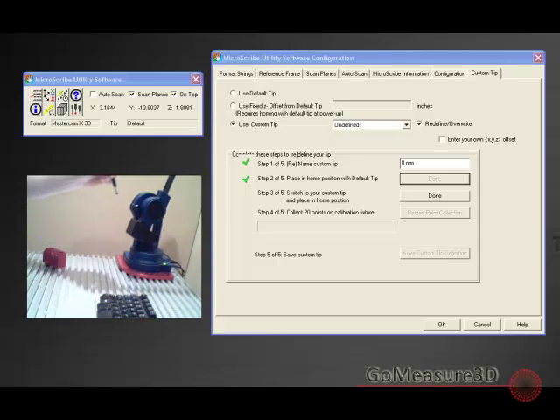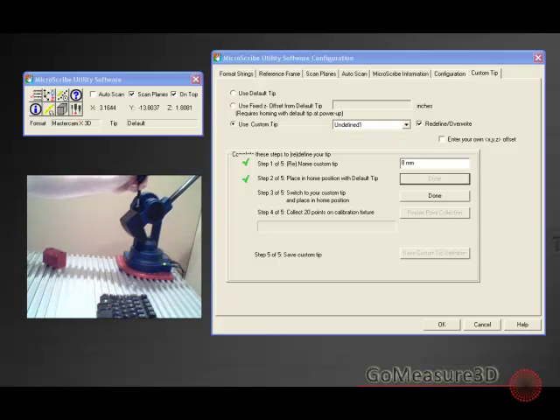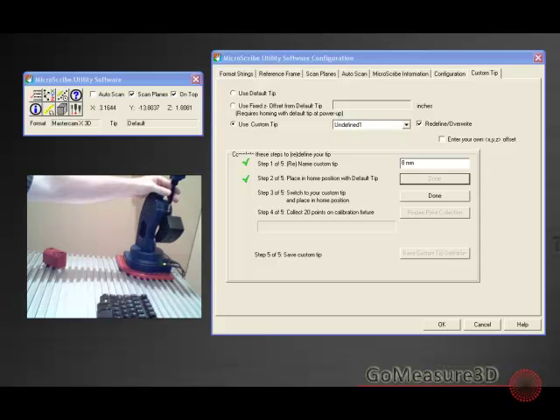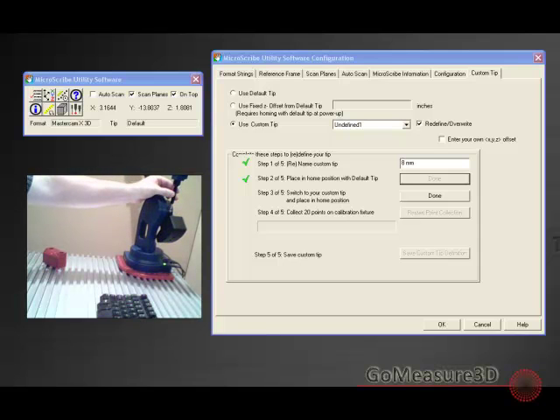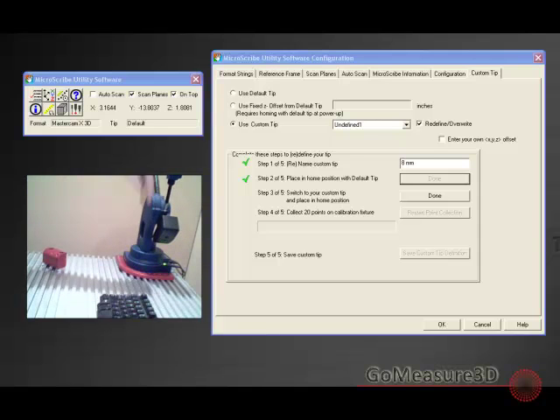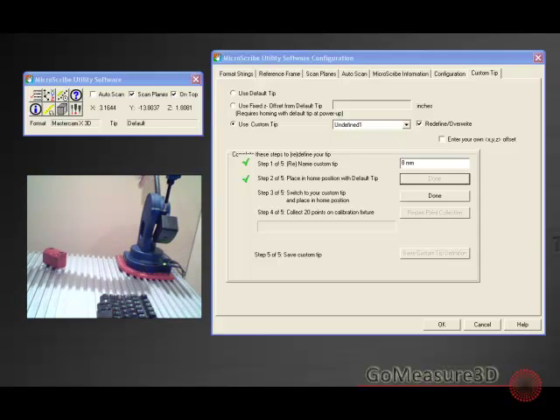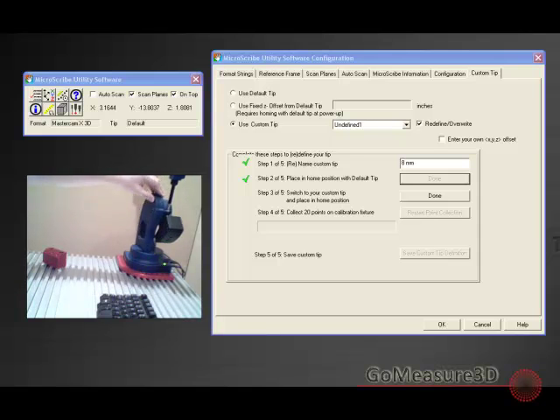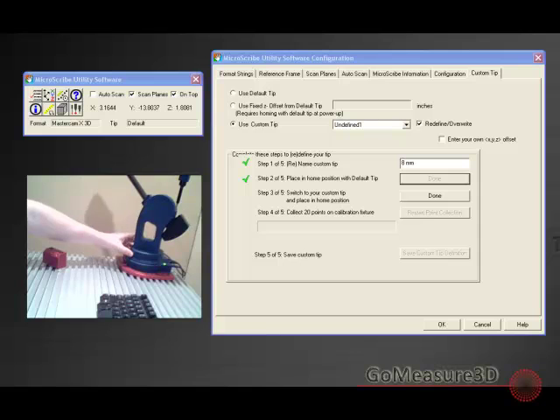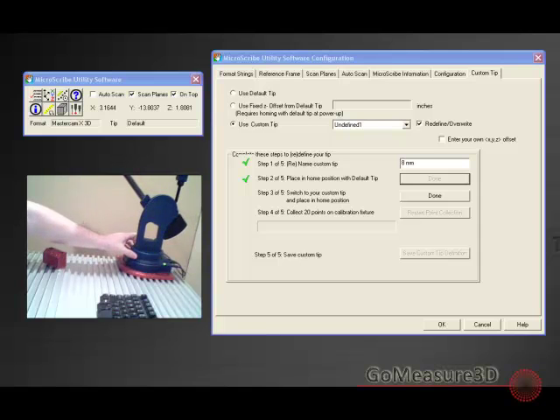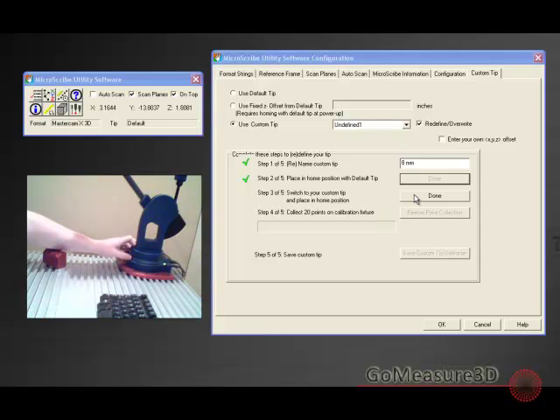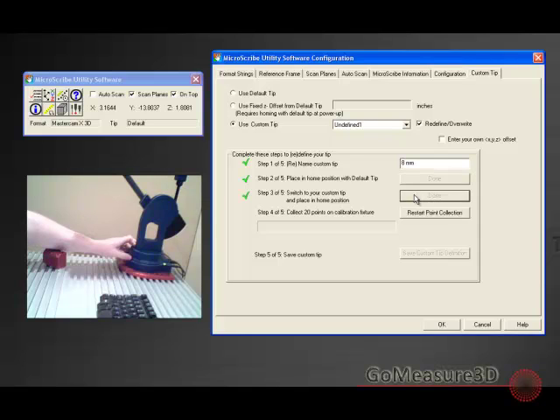Use our tip wrench to snug the probe into place. As it says, we want it back in the home position. So we'll rotate it. Let's go ahead and rotate our six axis. Again, we're rotating it as looking from the ceiling to the table and counterclockwise means at least 360 degrees and we'll line up the hash marks and then we'll bring the base of the microscribe into position. Again, do not hit the white button on the back of the microscribe, but instead come over and press this button to say done.